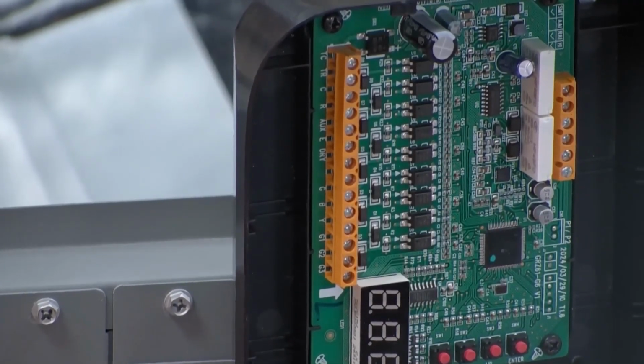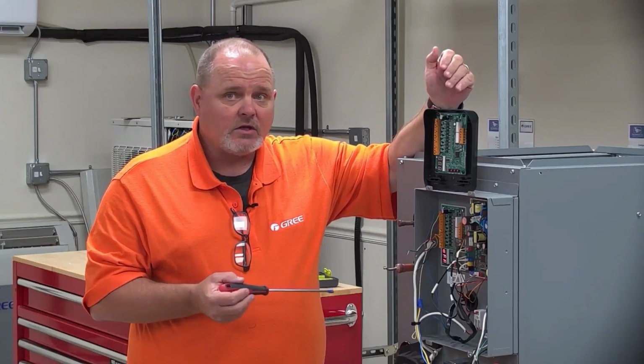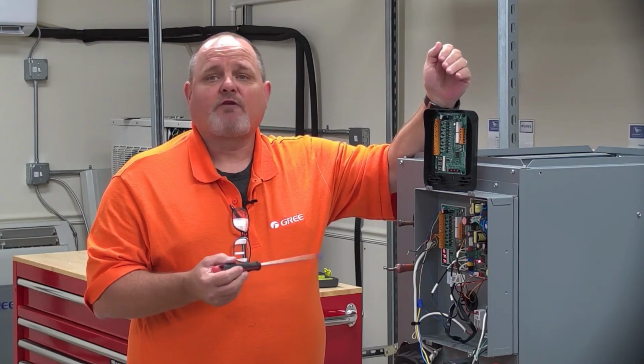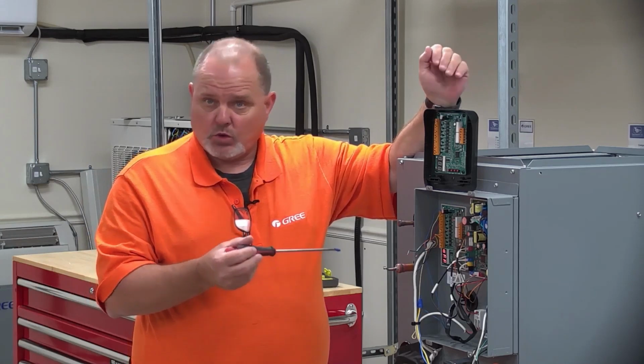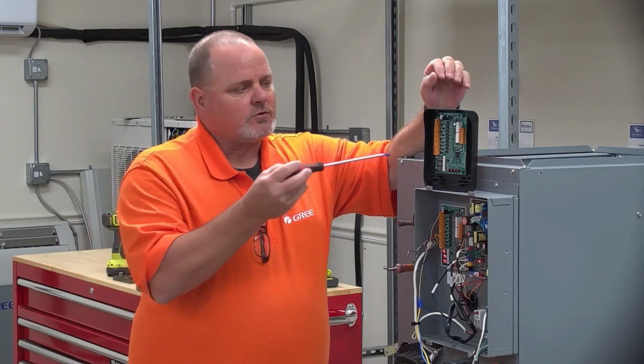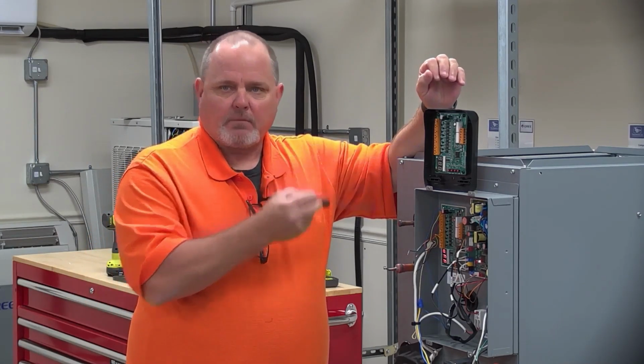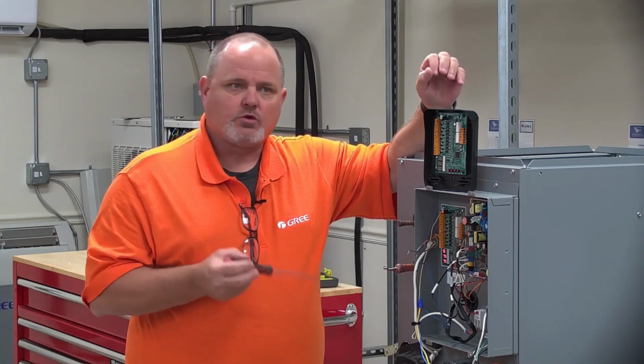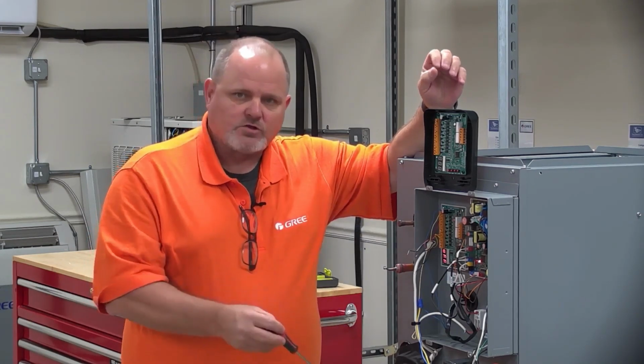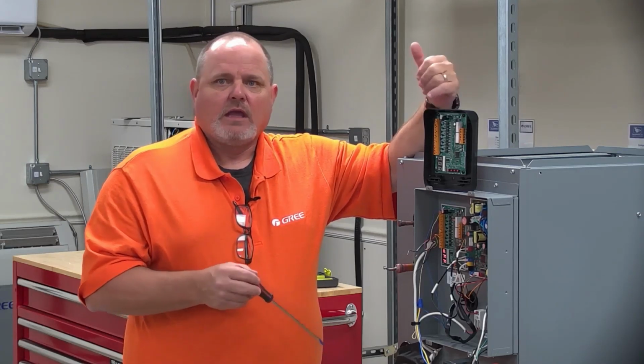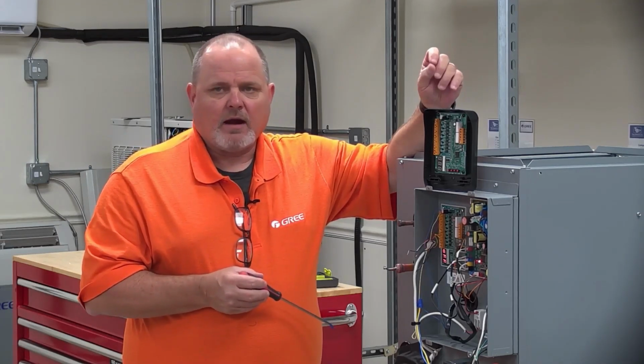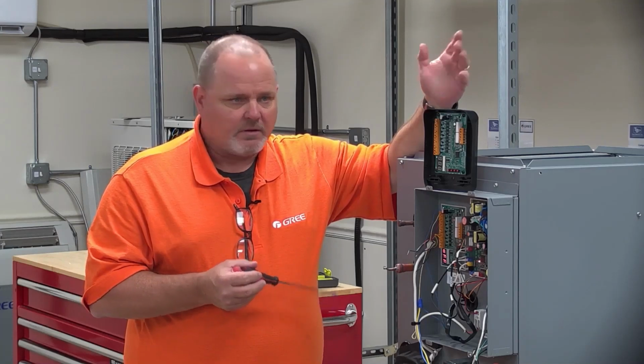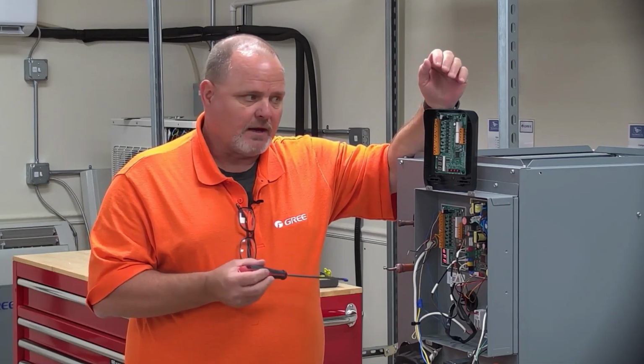Now, if your furnace is multiple speed, in other words, you would get a higher fan speed off of Y than you would G, you could always sister Y there and bring it down to your furnace as well. So when you get that Y call, the furnace board also gets the Y call, and it's going to ramp the blower up higher than the G speed. Depends on what furnace you're using, so keep that in mind.